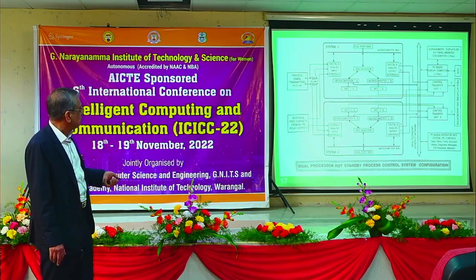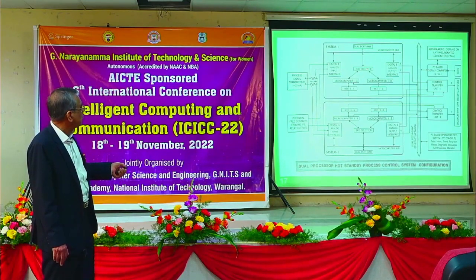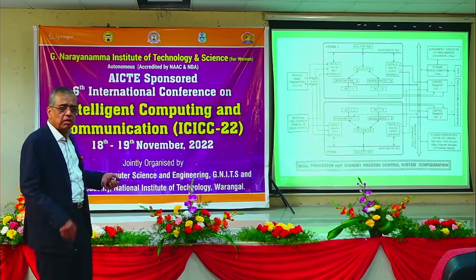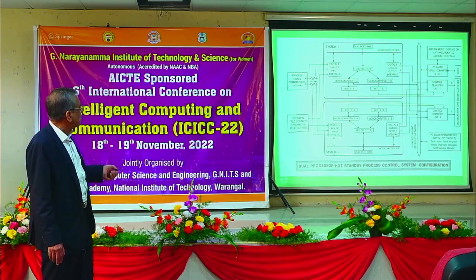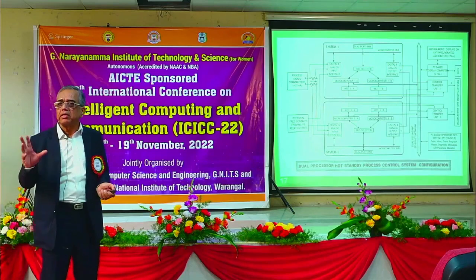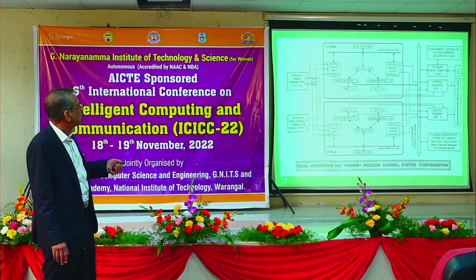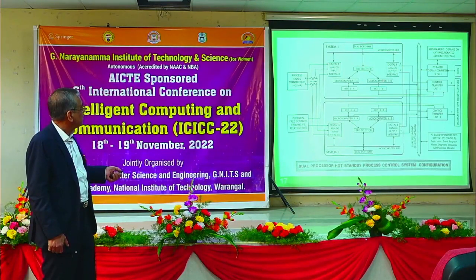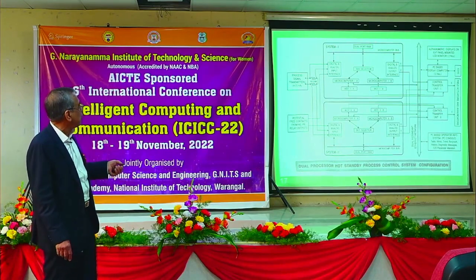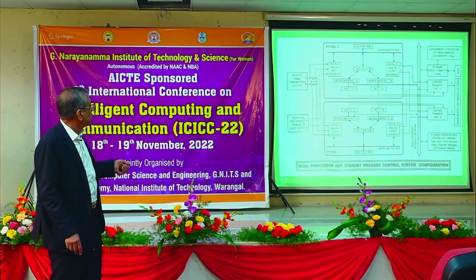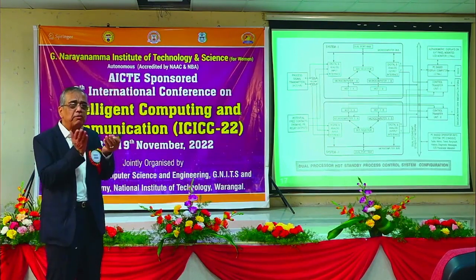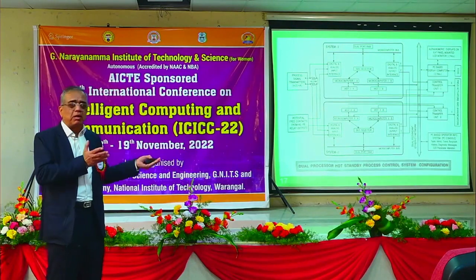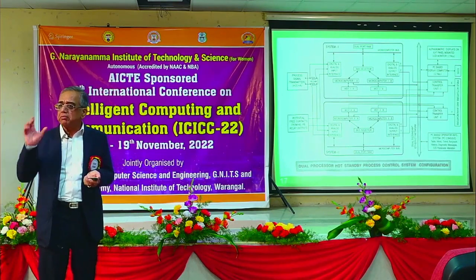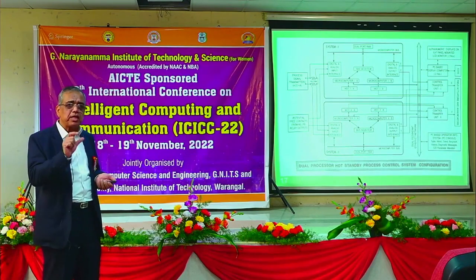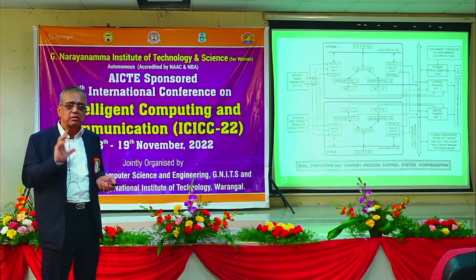There are two microcomputers in each system: 1A, 1B and 2A, 2B. Microcomputer 1A is connected through the bus selector. When the software starts, the microcomputer reads all the analog and digital inputs, processes them, and generates the output, which is written in a dual port RAM at some memory location. Then microcomputer 1B reads all inputs through the bus selector and writes its output to another location. Microcomputer 1A reads that output through the dual port RAM and sees whether the outputs are matching or not. If 1A and 1B outputs are not matching beyond a certain limit for, let us say, 3 software cycles, where one software cycle is 100 milliseconds, that means the system has failed.